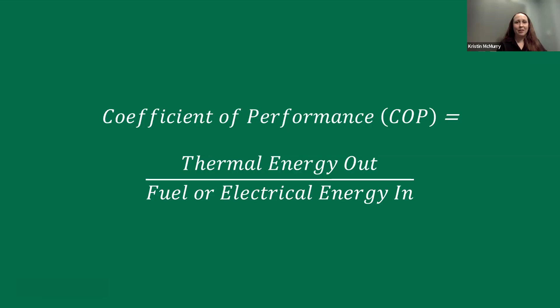So this is a little bit of a different term, and it's one of the most important things - if you take away nothing else from this, take away COP. It's very important, and the higher your COP, the better your efficiency. That ratio ends up as a number we assign to a specific piece of technology, and we'll say something has a COP of 1 if it puts out as much energy as it uses.